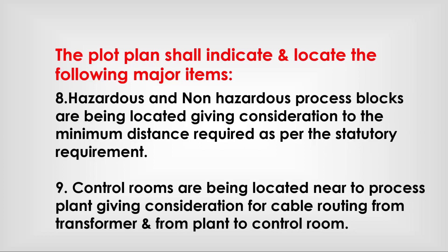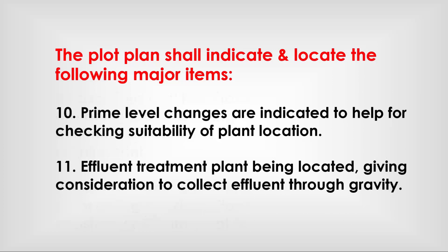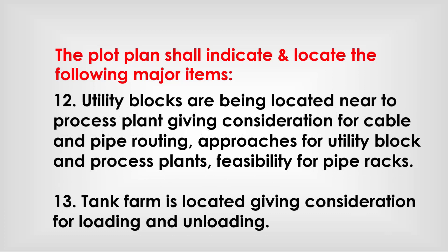Control rooms are located near the process plant, giving consideration for cable routing from transformers and from the plant to the control room. Prime level changes are indicated to help check suitability of plant location. The effluent treatment plant is located giving consideration to collect effluent through gravity. Utility blocks are located near the process plant, giving consideration for cable and pipe routing.